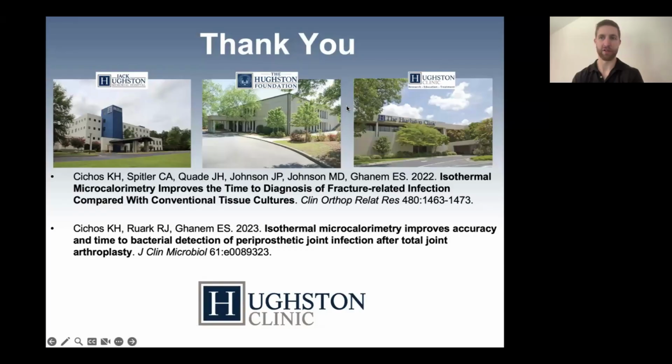may be sufficient. We learned that certain either slow growing bacteria or maybe just a small initial inoculum takes a little while to get there, and sometimes 24 hours wasn't quite enough duration on the runtime early on. We definitely missed a couple. I can think of staph epi being one that's typically pretty slow growing, and I know we missed a couple of those that were likely present and would have been detected if we had extended the run a little bit longer. But again, we learned from that.